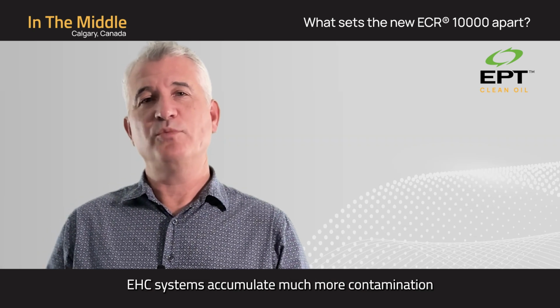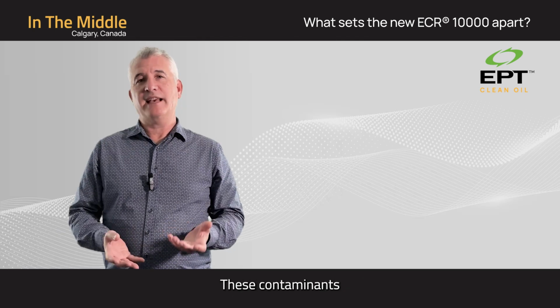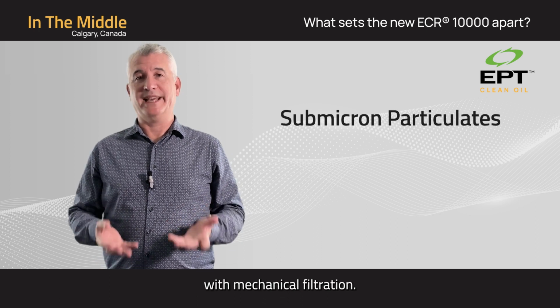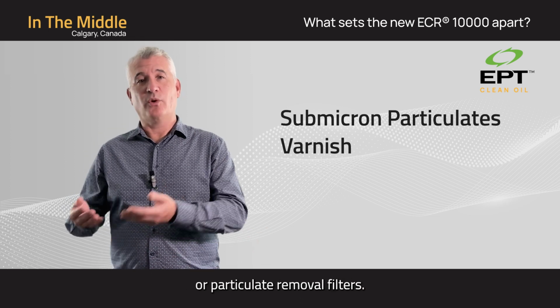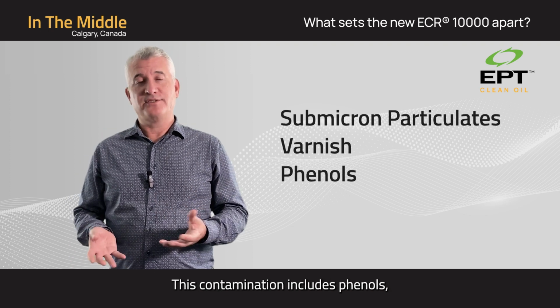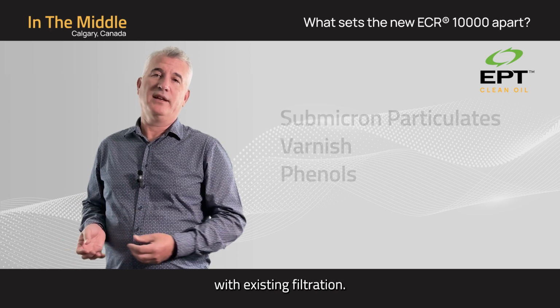EHC systems accumulate much more contamination than just particulate and acid. These contaminants include submicron particulates that are not able to be removed with mechanical filtration. They also include varnish that can't be removed with existing acid removal filters or particulate removal filters. This contamination includes phenols, which are varnish precursors that are not removed with existing filtration.